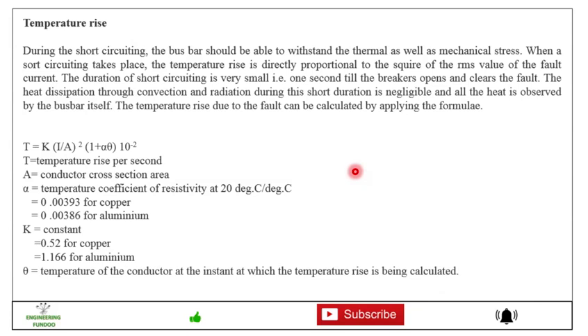So the temperature rise due to the fault can be calculated by applying this formula. Here T is the temperature rise per second, A is the conductor cross section area, alpha is the temperature coefficient, it is 0.003934 for copper, 0.003864 for aluminum. K is the constant 0.52 for copper, 1.166 for aluminum, and theta is temperature of the conductor at the instant at which the temperature rise is being calculated. And by using this formula we can calculate the temperature rise per second for the given busbar.